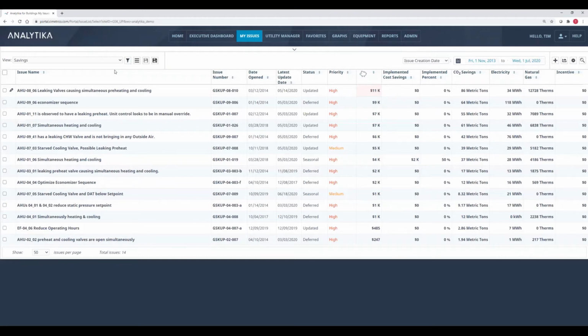We actually create a model or an emulation of the equipment in the building within the Analytika diagnostic engine. The way we do that is by populating our database with the points we get from the BAS. So when we populate our database with that set of 30 or 40 points from that particular air handler we were just looking at, our database now knows what type of air handler it is, what kind of coils it has, what kind of valves it has. We have all of the operational information - the signals, the positions, the flows, the temperatures, the pressures.